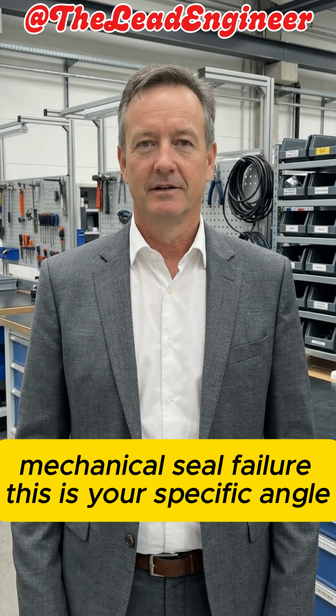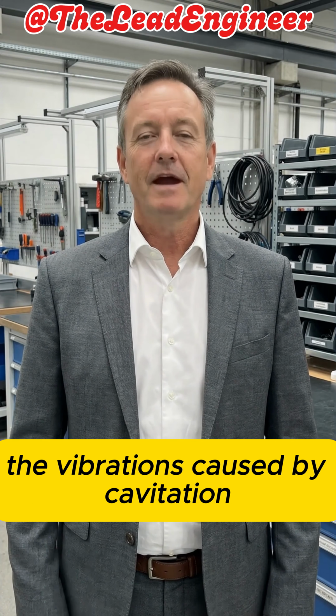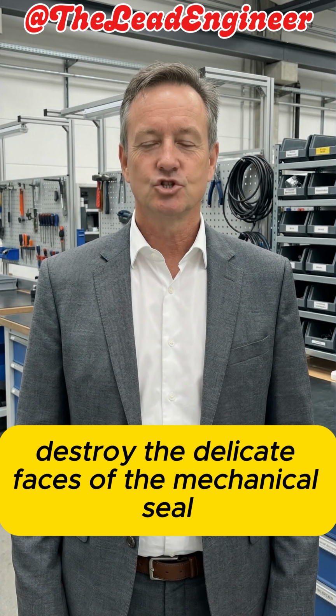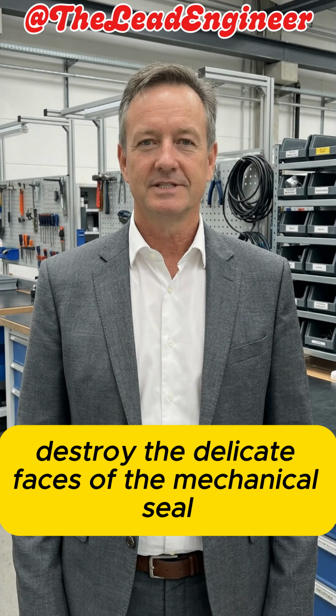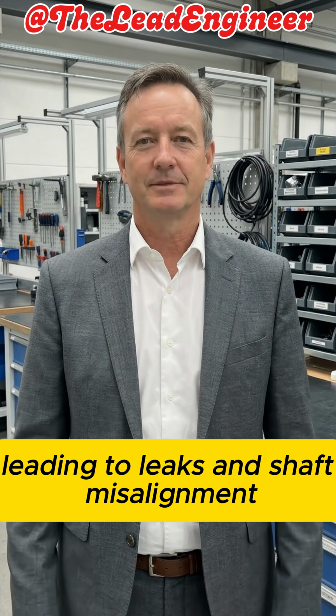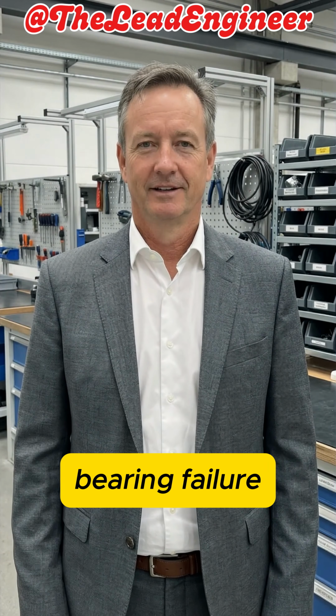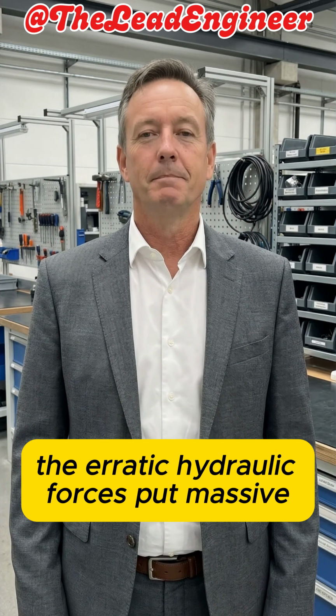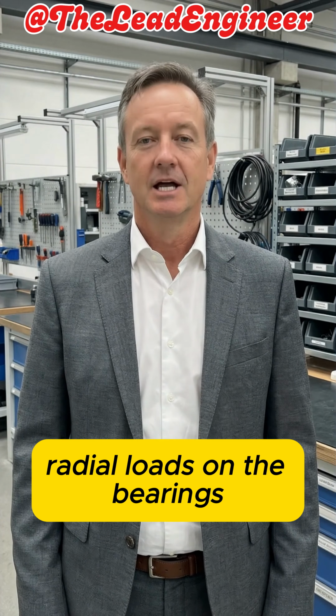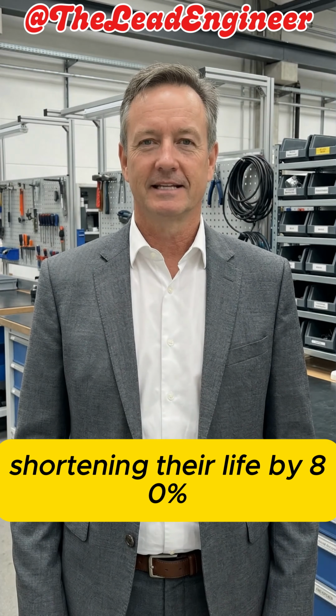Mechanical seal failure. This is your specific angle. The vibrations caused by cavitation destroy the delicate faces of the mechanical seal, leading to leaks and shaft misalignment. Bearing failure. The erratic hydraulic forces put massive radial loads on the bearings, shortening their life by 80%.